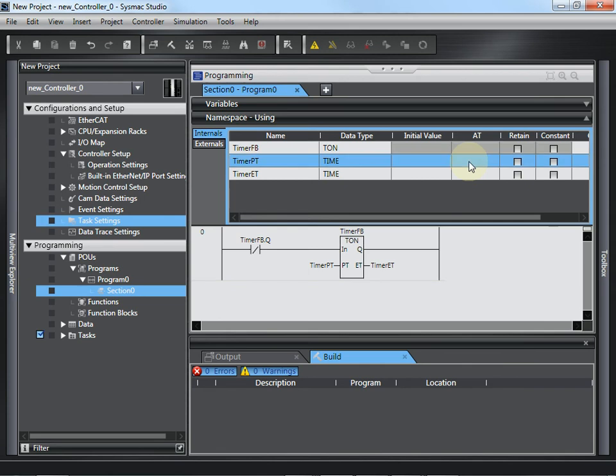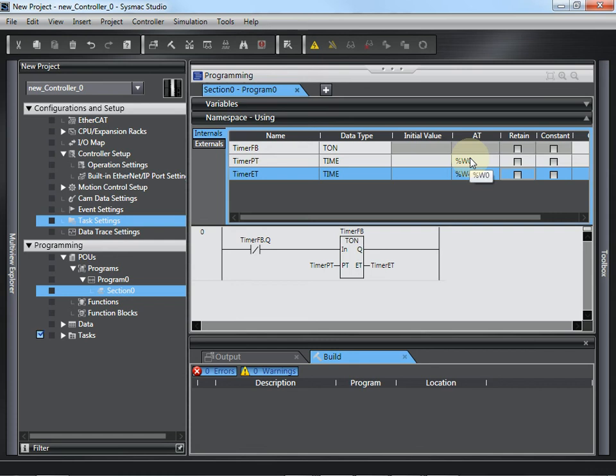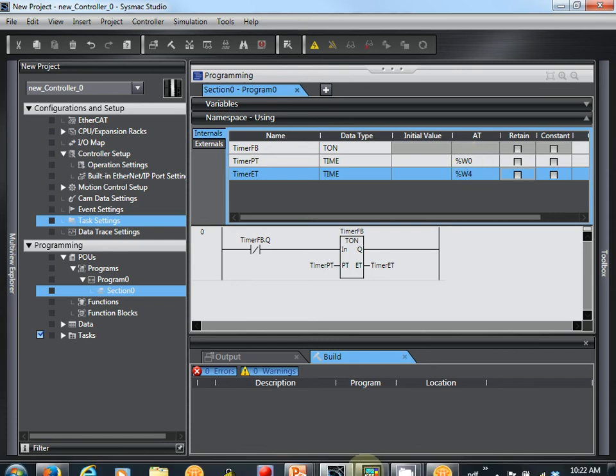So, now over in the AT column, I'm going to put %W0 for the first variable. Each one of these takes up four words because it's a long integer. So, the next one available would be W4. And that's all we really need to do on the PLC side. Let's now go to CX Designer.